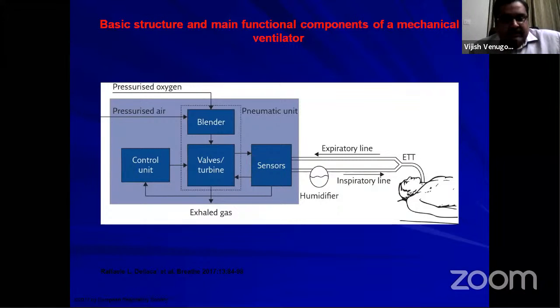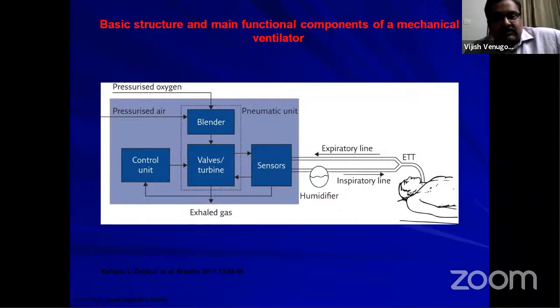So if you cut open a ventilator, this is how it would look. You would have lines, the pressurized oxygen and the pressurized air, coming into a blender, which is the pneumatic unit. And from the blender, the desired FiO2 will go through the drive mechanism, which could be the turbine. And this is controlled by the control unit of the ventilator. And of course, when the gas goes out, it goes out through the sensors.